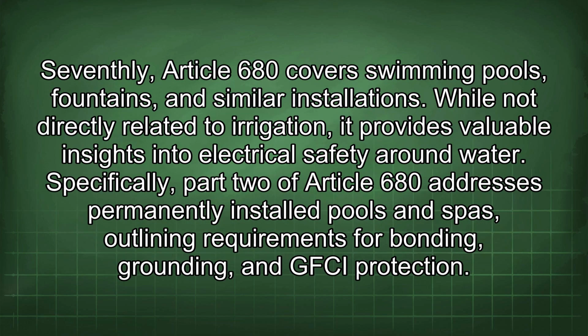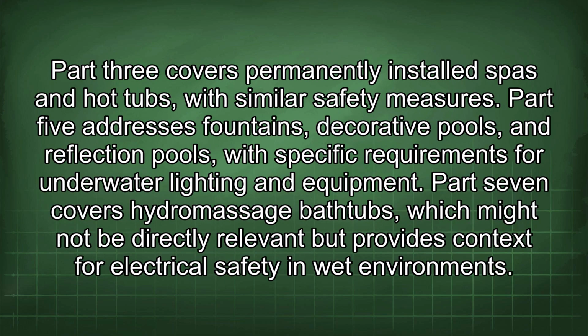Seventhly, Article 680 covers swimming pools, fountains, and similar installations. While not directly related to irrigation, it provides valuable insights into electrical safety around water. Specifically, Part 2 of Article 680 addresses permanently installed pools and spas, outlining requirements for bonding, grounding, and GFCI protection. Part 3 covers permanently installed spas and hot tubs with similar safety measures.